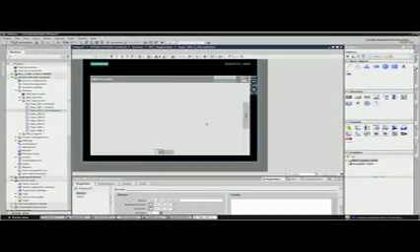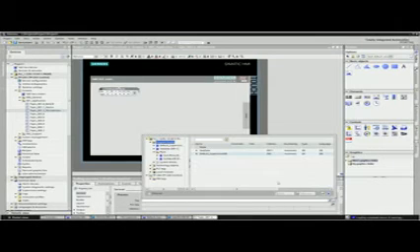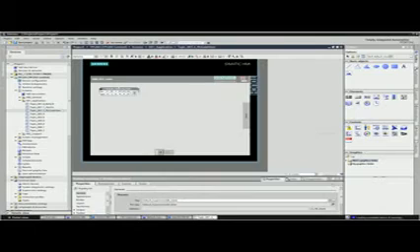How do you display the process diagnostics information on the controller? To do this, the TIA portal offers a range of screen objects which you simply drag into an HMI screen. The ProDiag overview gives you an overview of the current status of the configured supervision. Now you just assign the status tags from the ProDiag function block to this overview. Done.